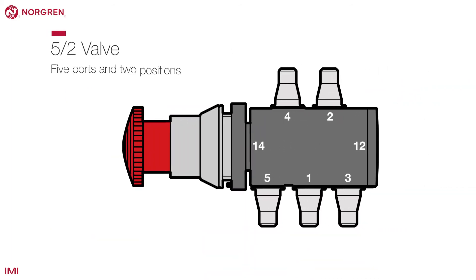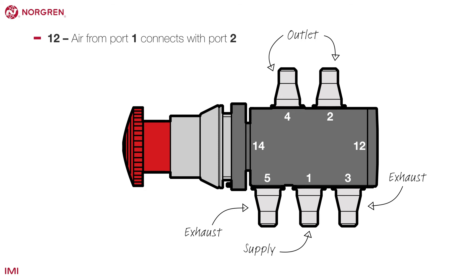A 5-2 valve has 5 ports and 2 positions. As you can see here, there is still 1 inlet, but now there are 2 outlets and 2 exhausts. The 2 positions are air to port 2 outlet or air to port 4 outlet, so the operation for this valve would be 1-2 and 1-4.